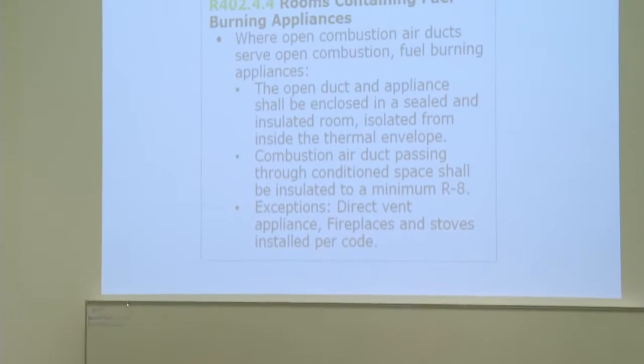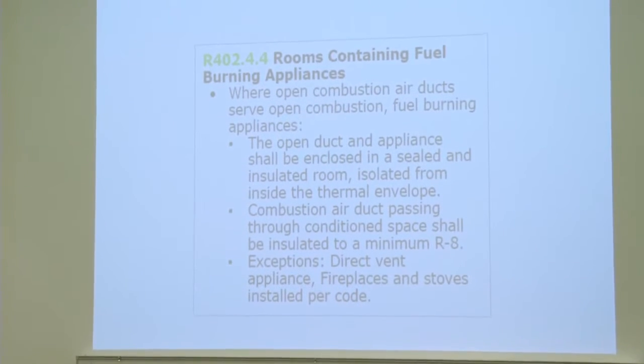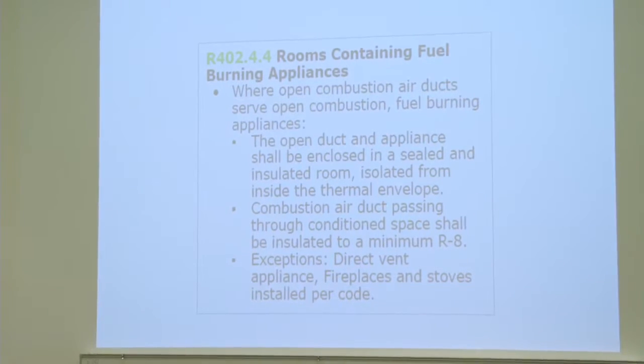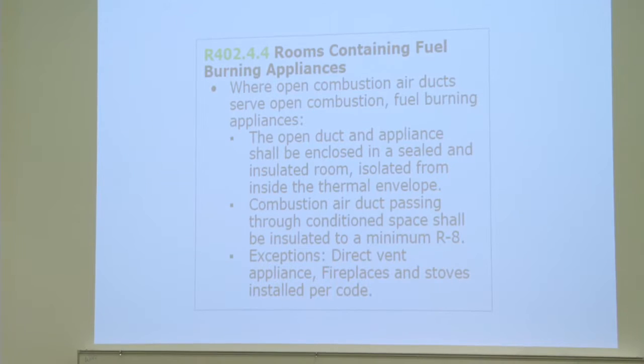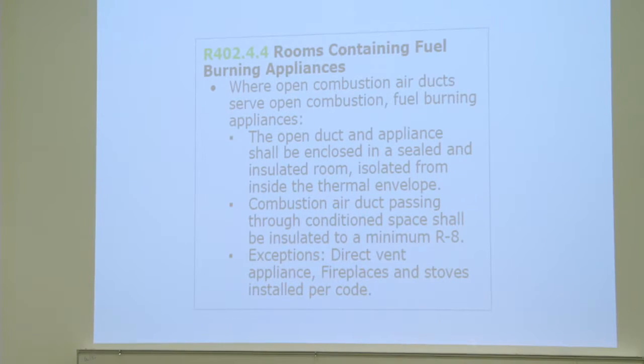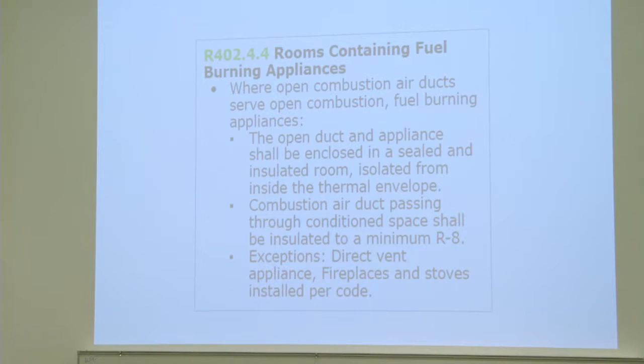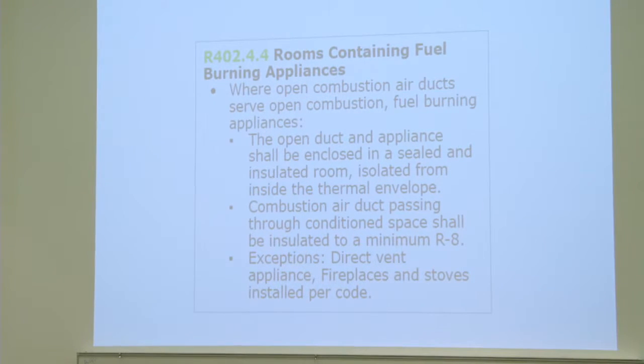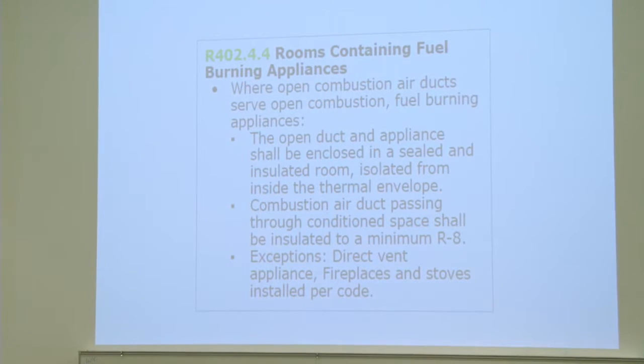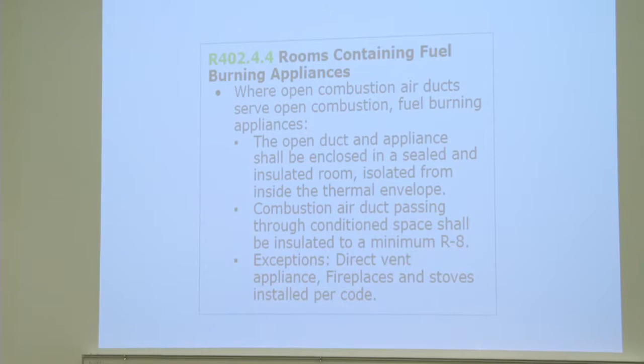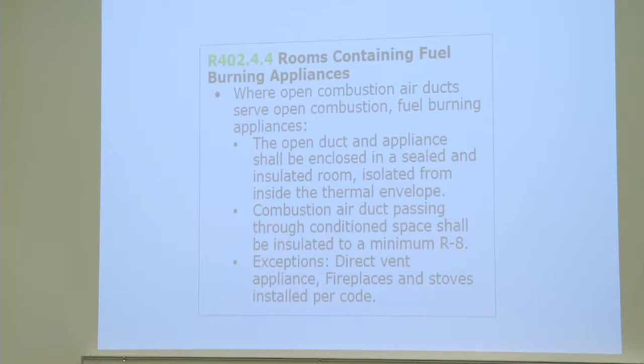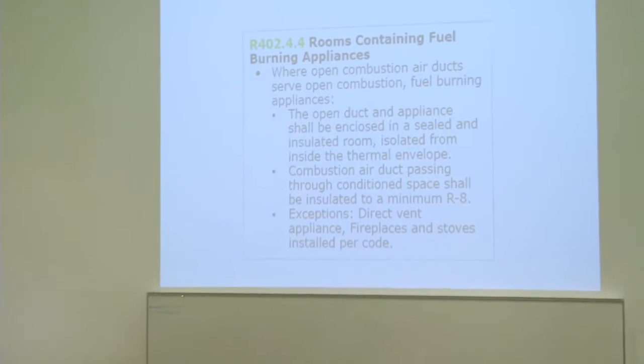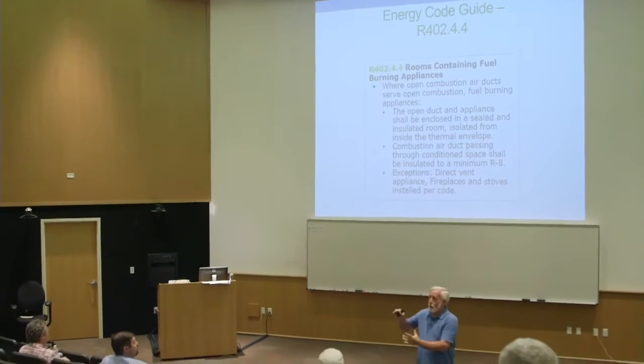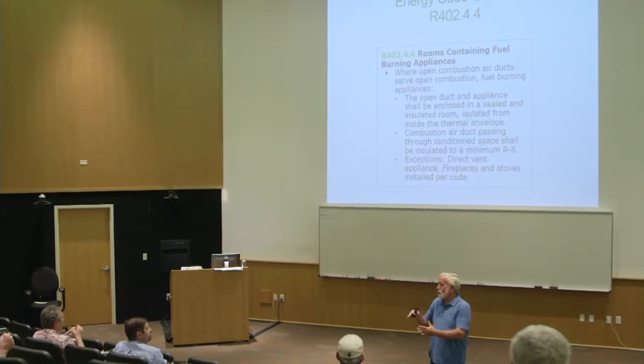Rooms containing fuel-burning appliances. I still remember, I don't remember the year exactly, but I think it was someplace around 1985, 1986, when Questar at the time came out and said, we have to bring combustion air into all of our furnaces now. We can't rely on infiltration. We've made the house tight enough that we have to cut a hole in the house. And it just has never made sense to me. And some jurisdictions, as they read the code and the sections that said we had to do these different things to tighten up the house, have interpreted, and I think rightly so, that an open combustion air duct really doesn't meet the code requirements for air sealing.